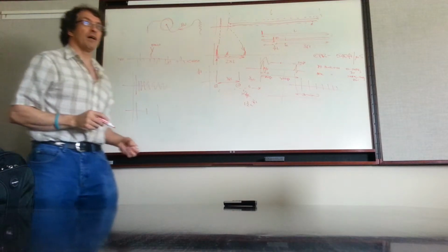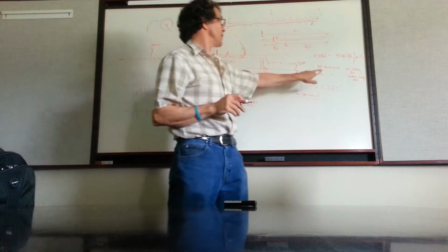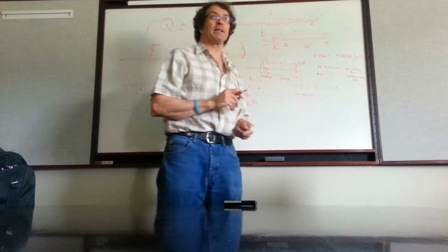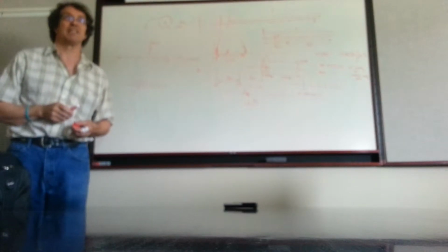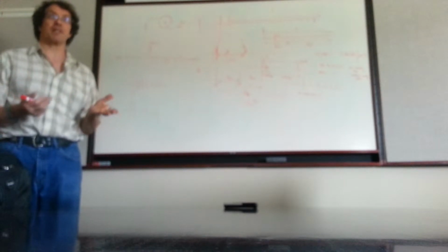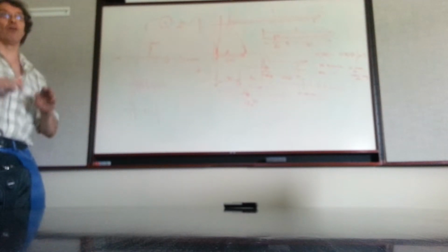So you'll probably find a lower level PD fault with the PD amp than with the PDSL, because you saw our background noise looked like 7 or 8 or even 9 pC with the PDSL amp. So if you had a 5 pC fault on the PD amplifier when you were testing it, when you switch to the PDSL you would never see the fault. It's just lost in the noise.